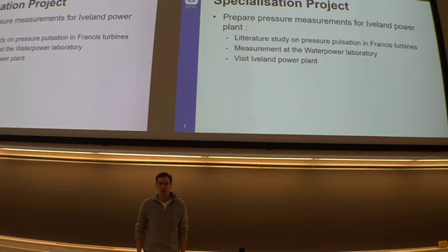My specialization project is to prepare pressure measurements at the Iveland power plant. I've done this by doing a literature study on pressure pulsations in Francis turbines. And that has included what causes pressure pulsations, what damage they can do, and how to prevent them.